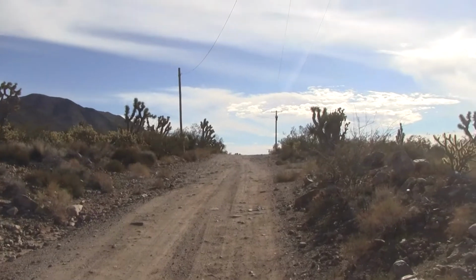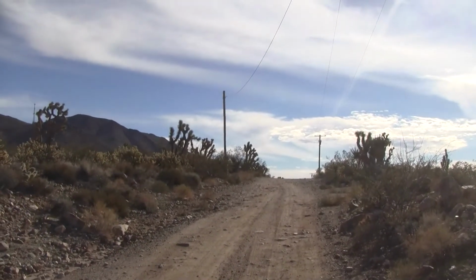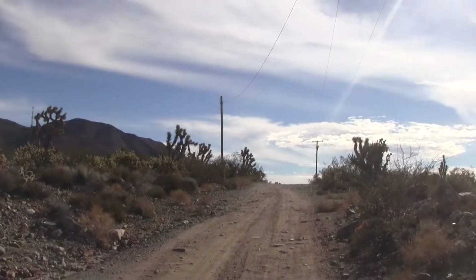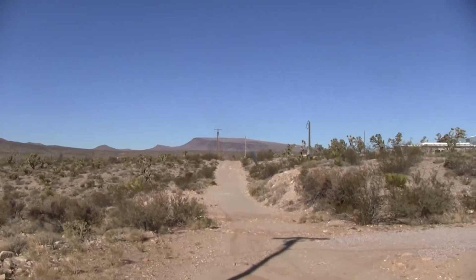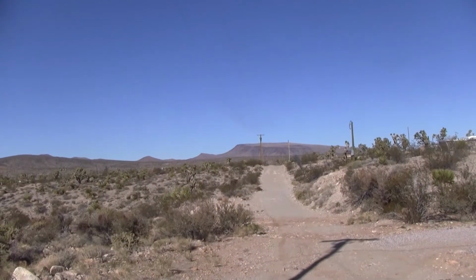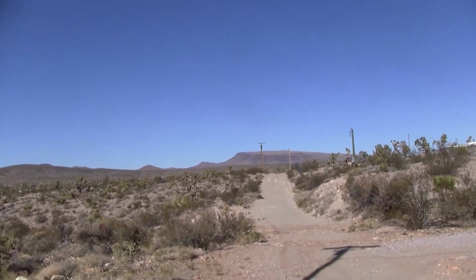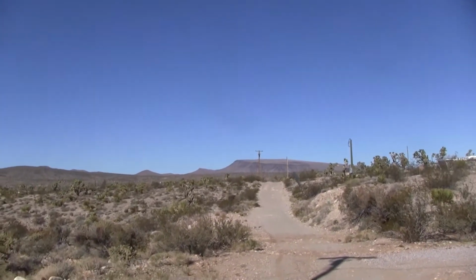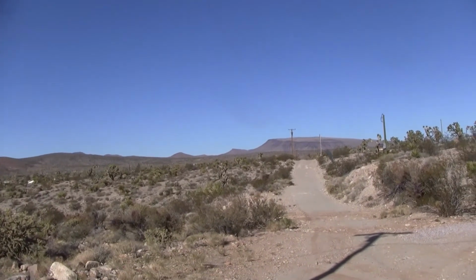See that pole there on the right with the transformer on it? I think that pole has a broken ground, and then a couple poles down at the intersection down there, there's a broken ground. And not the next pole you can see, but one pole after that, there's a broken ground, and another pole or two after that, there's another broken ground. So there's 4 of them in one block. That's not good. That's not good.